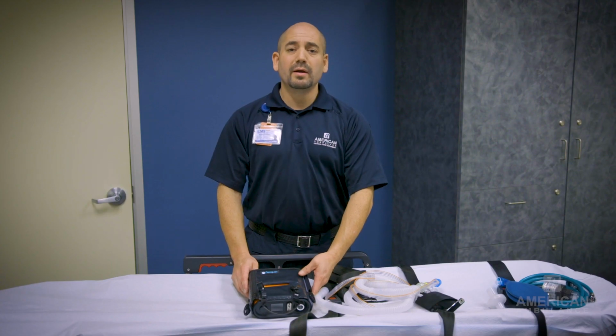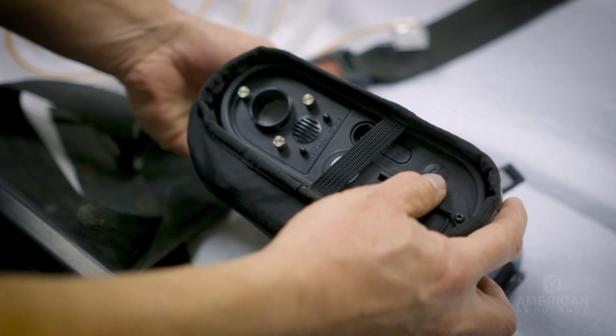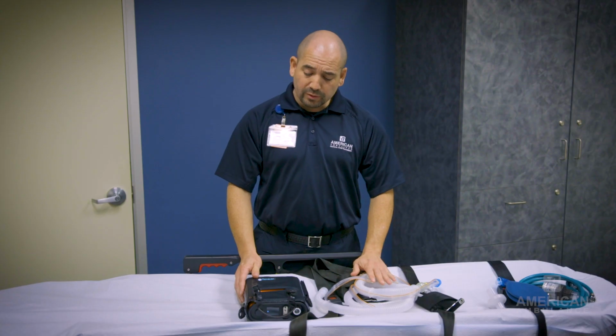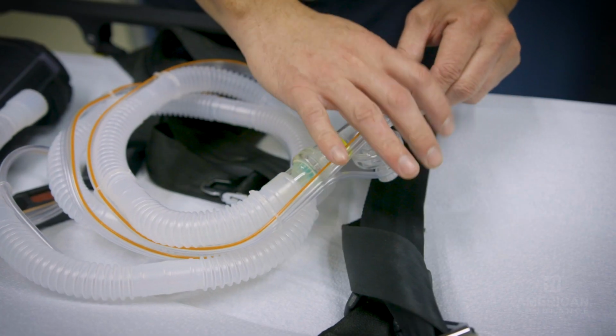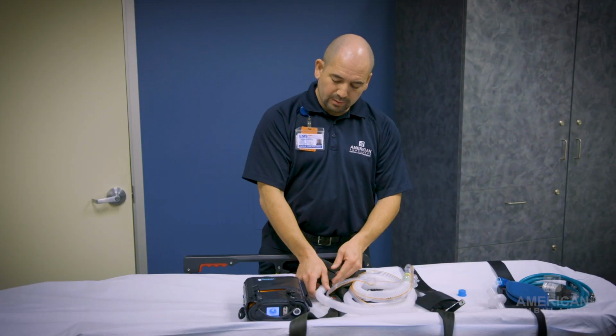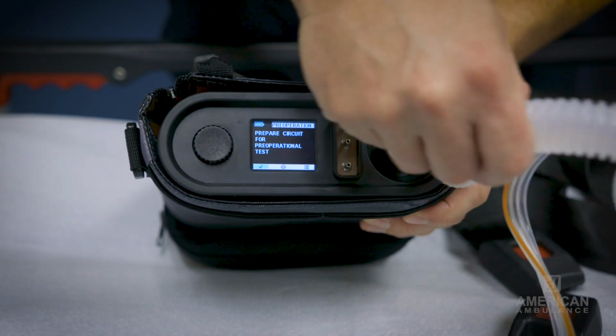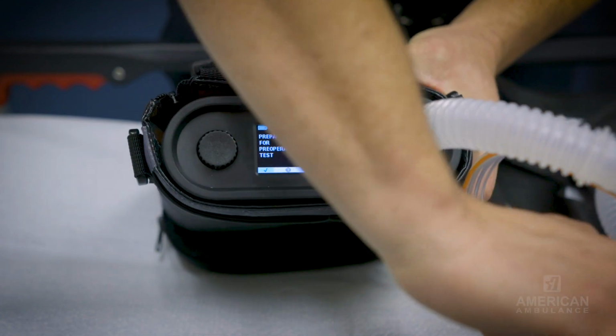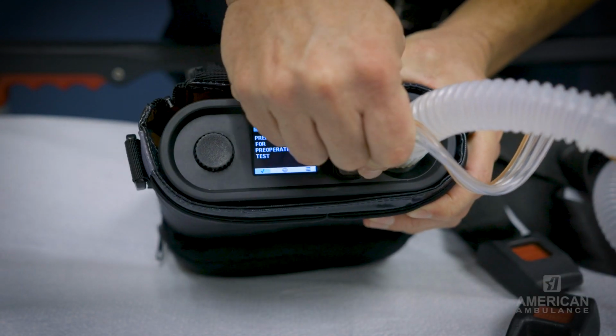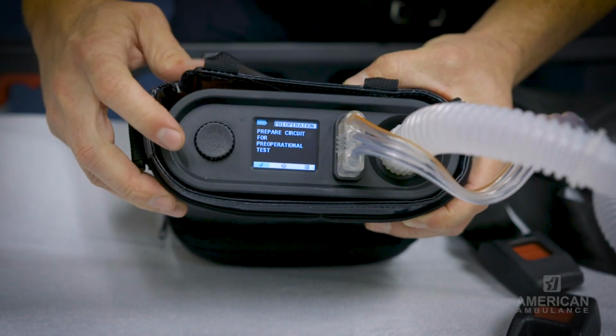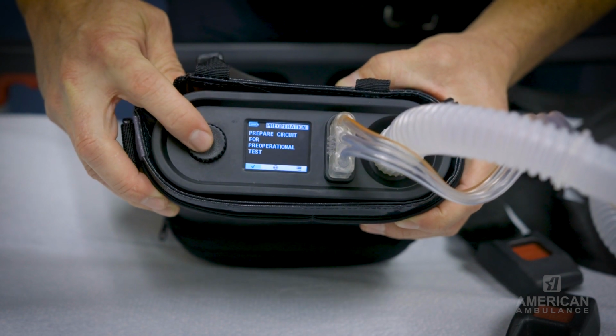After assessing the patient and getting the ventilator settings from the RT, it's time to turn on and set up the ventilator. Press the power button to turn on the ventilator. Remove the circuit from the bag and remove the blue cap. Plug in the circuit and plug in the sensor tubing. After it's plugged in, perform the circuit test by pushing the button.